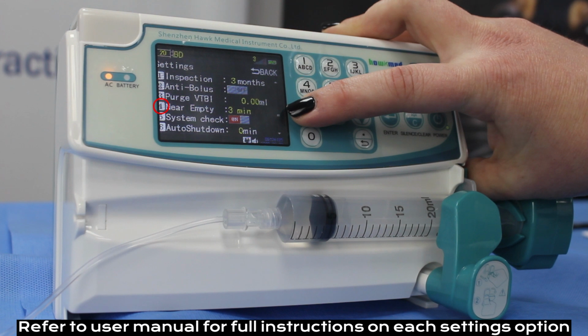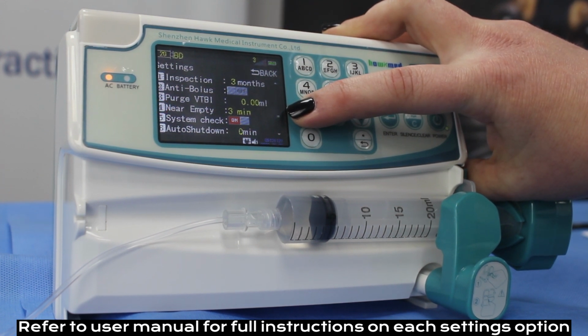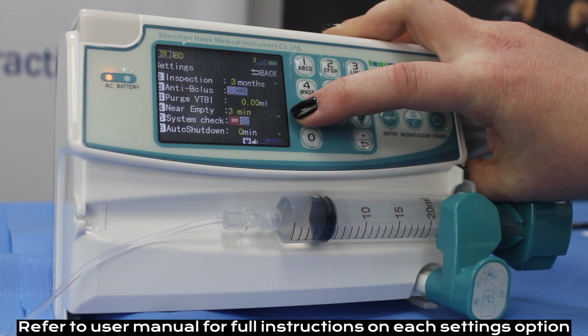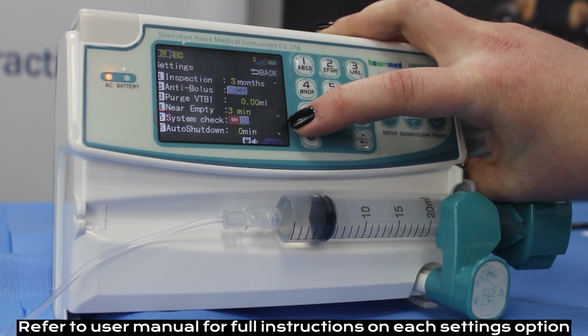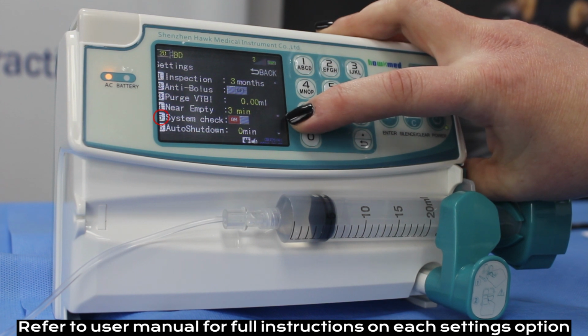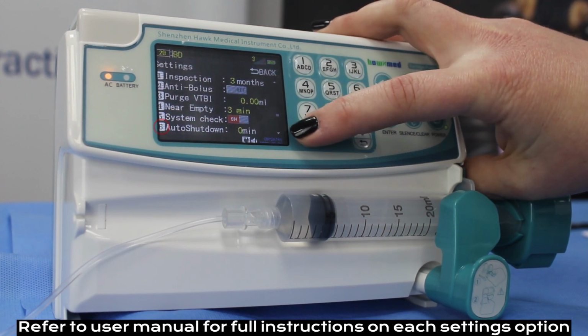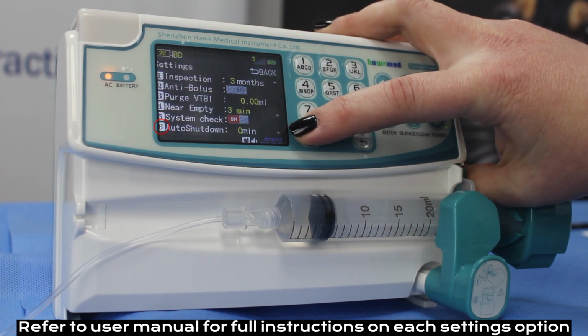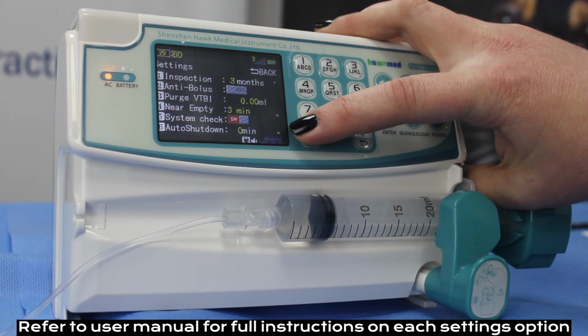Next down we have near empty. Near empty, different to when your volume to be infused will be finished, is the time duration of your infusion being close to finish. So when only 3 minutes of the infusion remains. Your system check should stay on, as this is a self-check system that performs on startup. And your auto shutdown can be set if desired, so that the pump shuts down automatically after a certain period of inactivity.